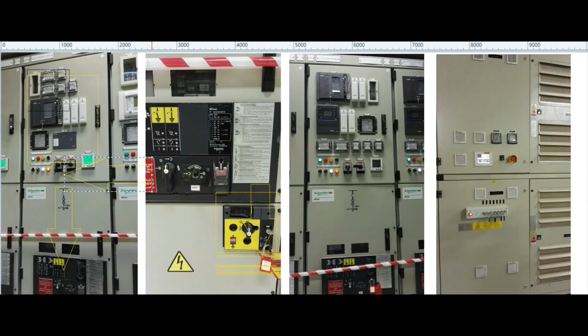And you see this panel is charged. This first panel, it is already charged because indication lamps are there. Indication lamps are glowing here. But in the second snap you can see this breaker is in test position and padlock is there. So some panels are charged and some are not energized yet.